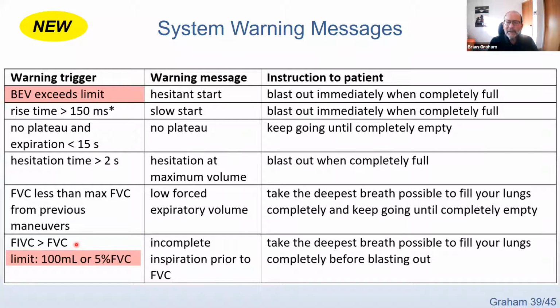The other thing that we've got is standardized warning messages. Now, pretty much every system had its own little warning messages, and some of them were worded differently, and it varied from one system to another. So we've tried to standardize that as well, and to say what are some of the things that the computer analysis can find out and tell the operator and the patient. The ones that are highlighted in red are things that would make the measurements unacceptable. So if the back extrapolated volume exceeds the limit, what happens there? The rise time, we did not make this an error that would make the effort not acceptable, because some people with muscle weakness and so on just can't initiate that flow really quickly.